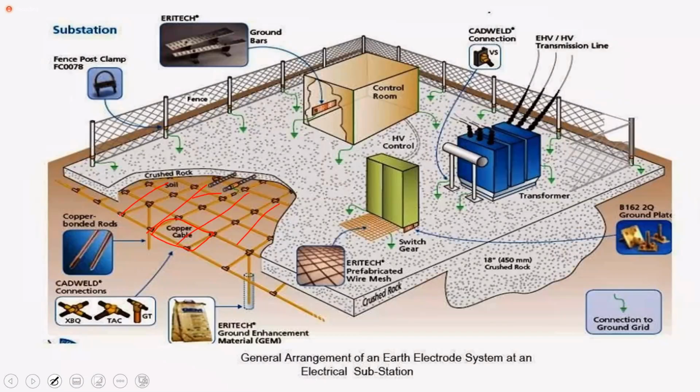Thirdly, you have some rods here. You see these rods? Well, they only show 2 here, but obviously there'll be more. You can increase the number of rods. Those are your vertical rods here. You can increase the number of meshes, so you'd use more wire. And you can make the grid itself deeper.